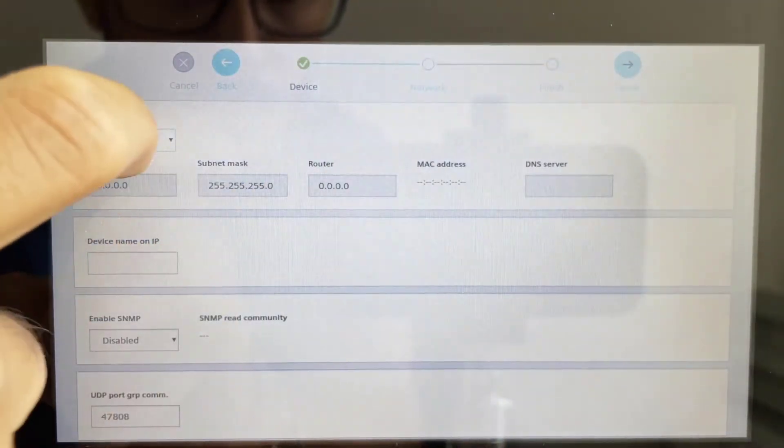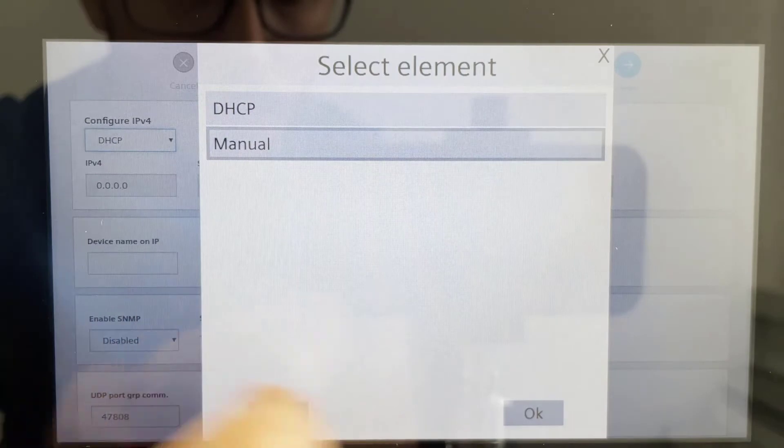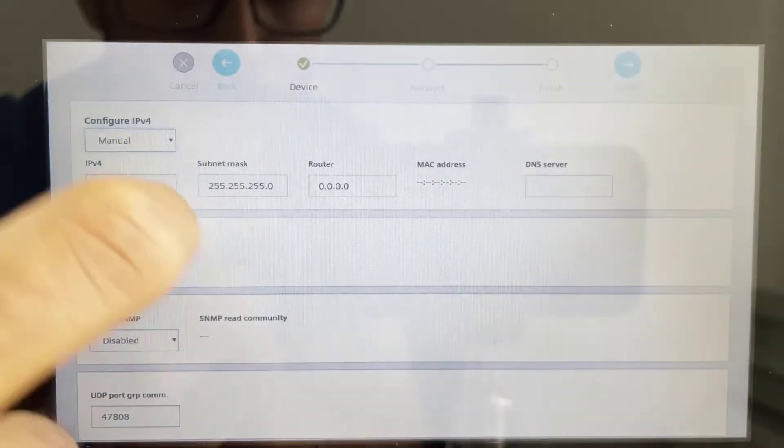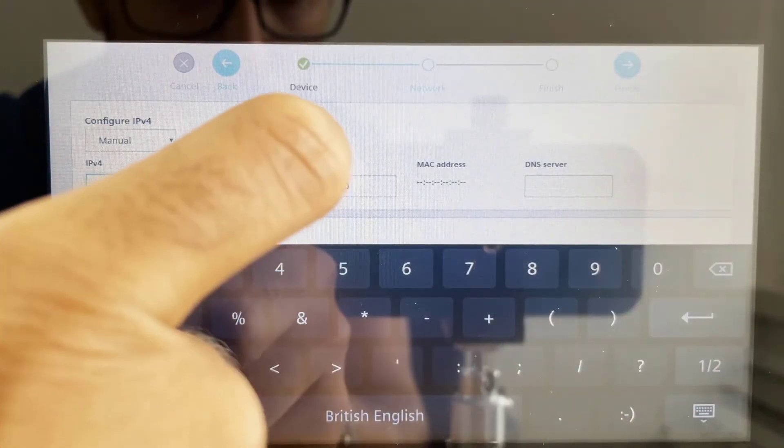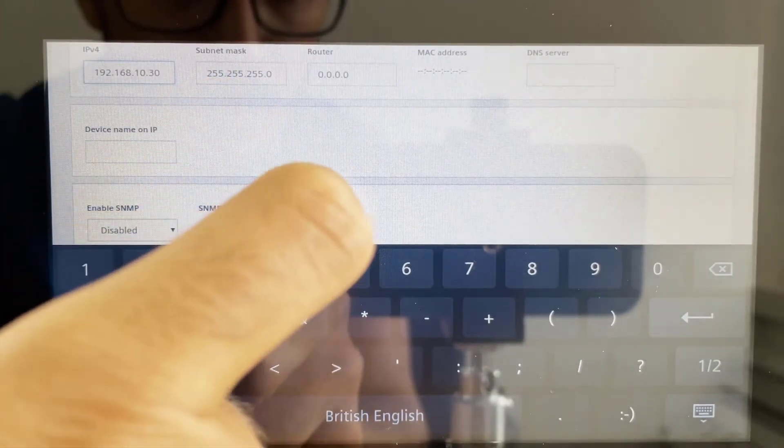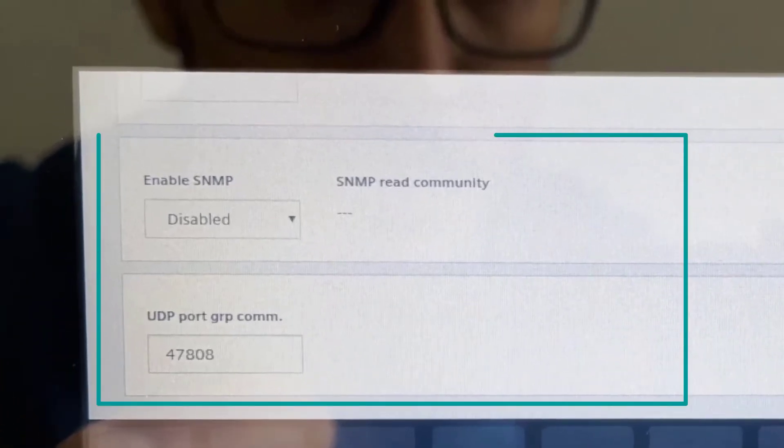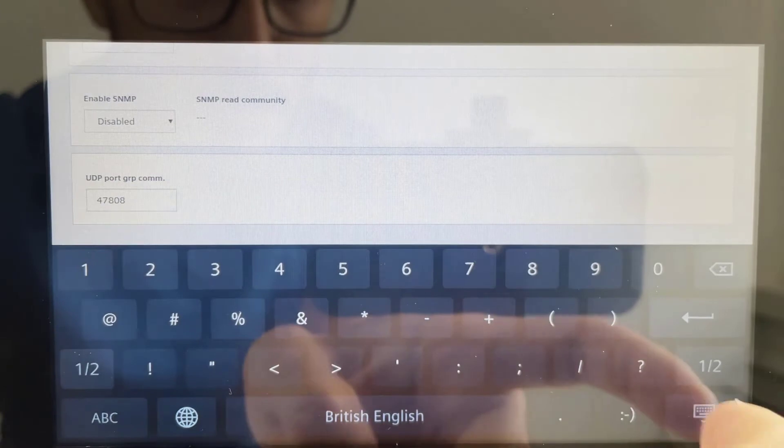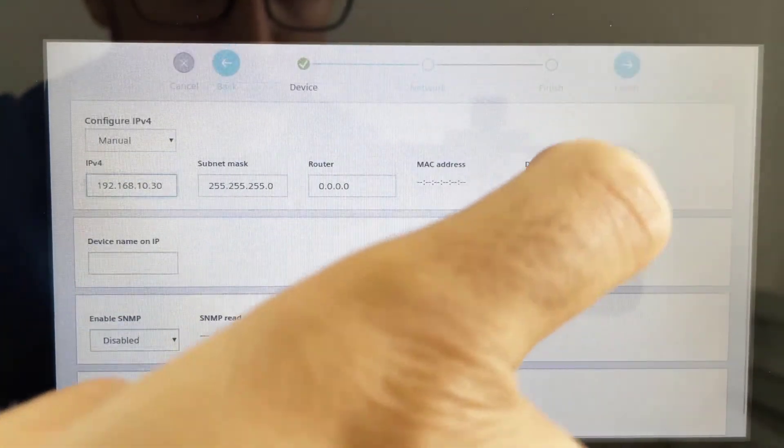Tapping on Next, the wizard gives the possibility to set up the network parameters, like enabling or disabling the DHCP function or setting up a fixed IP address with the proper subnet mask and router. SNMP option is also available to be enabled, then it's even possible to change the BACnet UDP port from the default one, if necessary.